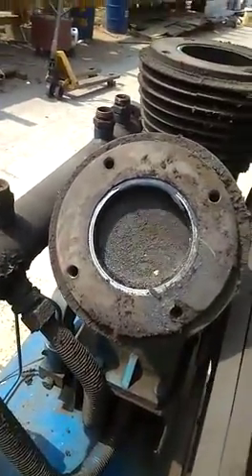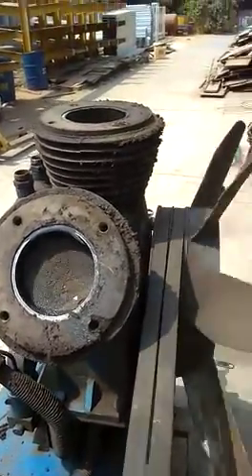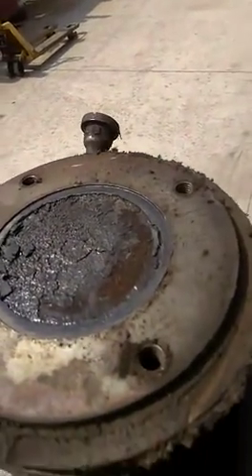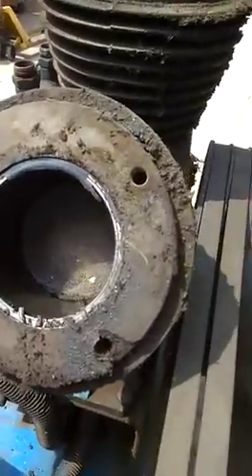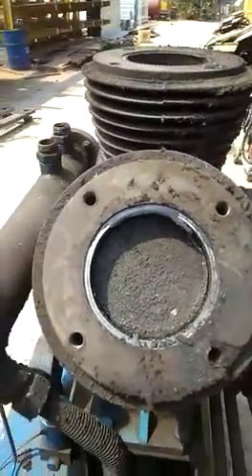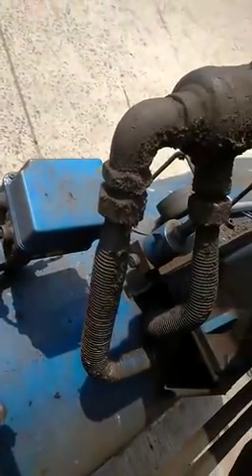When I rotate these, the piston cylinder assembly is moving up and down. This compressor is 7 to 8 months old with no servicing done, so there are too many carbon deposits on the piston assembly.